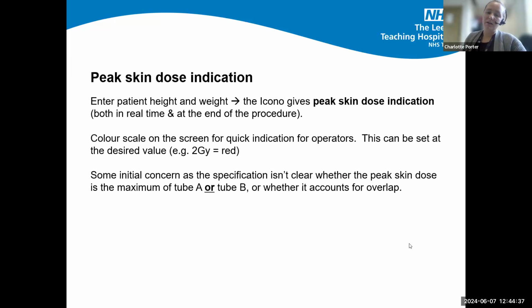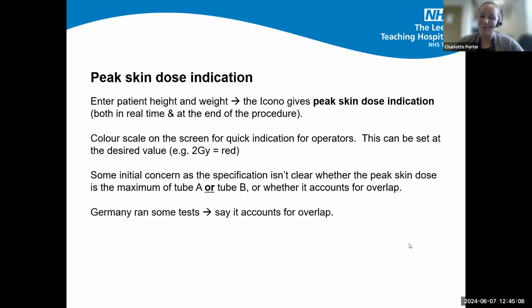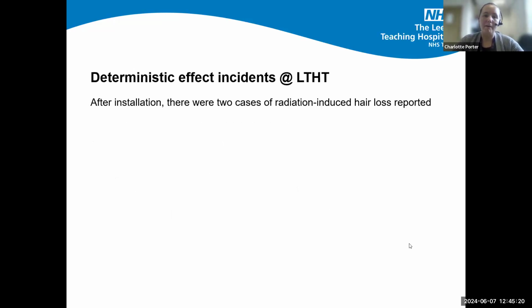We had some concerns initially, so we spoke to the application specialist. When we started getting some of these peak skin doses through, we weren't really sure exactly what was going on. The specification wasn't clear enough to establish whether that peak skin dose was looking at tube A, looking at tube B, and giving you the highest of the two values, or whether it accounts for the overlap. Our application specialist didn't know, so they fed that to Germany, and the person who got back to me said he didn't know either. So he went off and did some testing and said that, thankfully, it does account for the overlap, so that's good news. But we still have some queries about how accurate that peak skin dose indication is, as I will show you now.